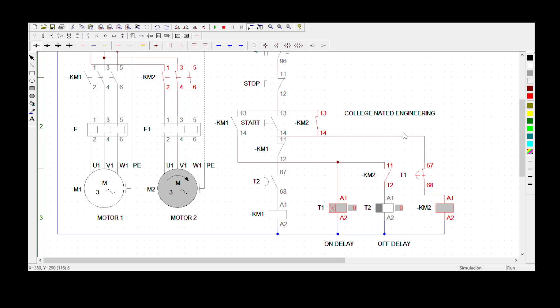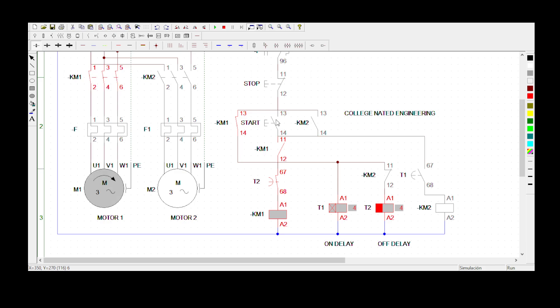Let me start the whole process so you can watch for yourself. I press the start button and Motor 1 starts rotating. Only after 10 seconds can we start Motor 2. After waiting, now the contact is normally closed, so we press the start button again — both motors are rotating. After 10 seconds, Motor 1 will stop and Motor 2 will continue running. Either motor can be stopped when the stop or emergency button is pressed.